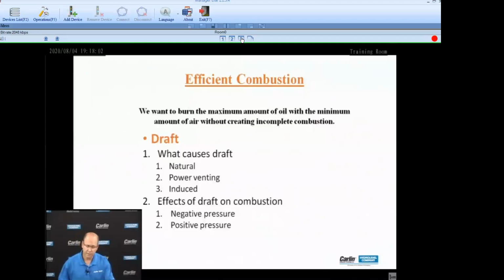We've got natural draft. We've got power venting and induced. Anytime you have mechanical draft, from my experience, I see oftentimes where a mechanical draft device is misapplied, too small, too large, not properly installed. All these things matter. Sometimes a mechanical draft device is installed because there was an issue with draft that was not fully understood. And by not understanding that the causes of the poor draft had more to do with the layout or the equipment or the firing rate or the appliance itself, they install something that becomes unnecessary and sometimes makes the problem a little bit more difficult to solve.